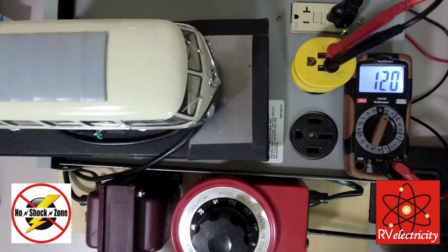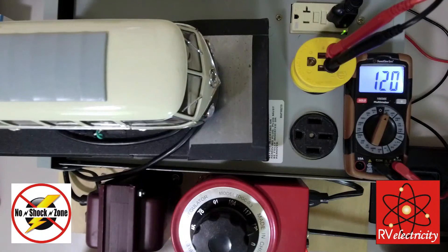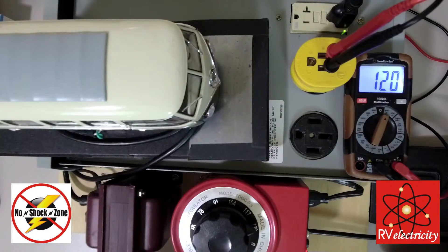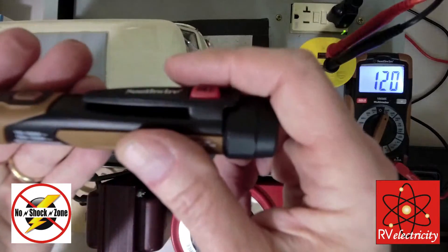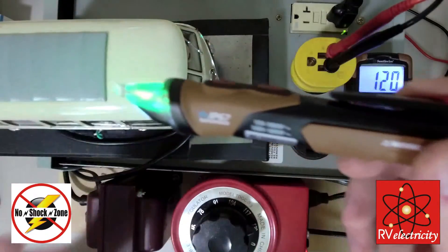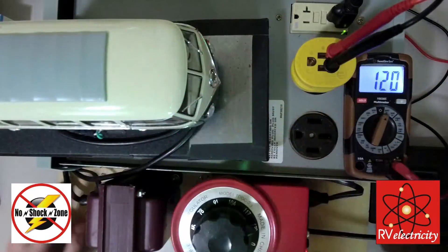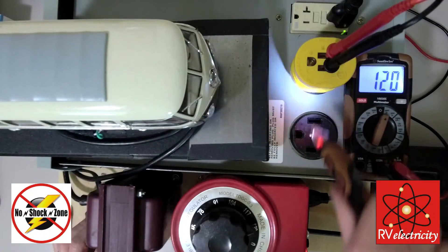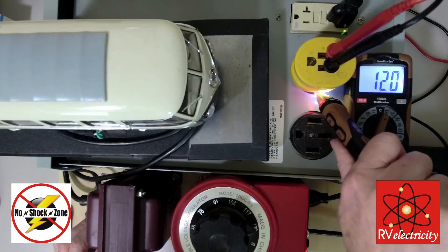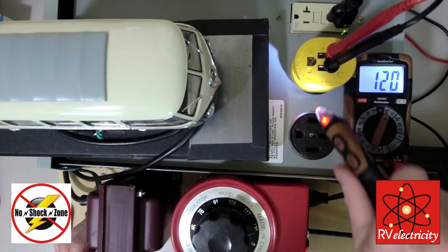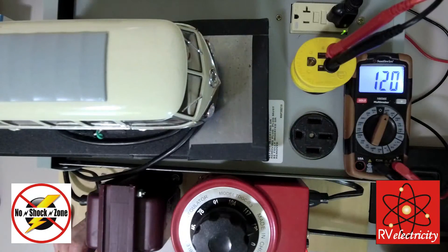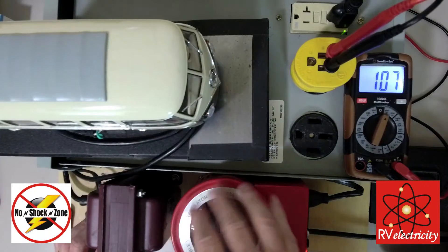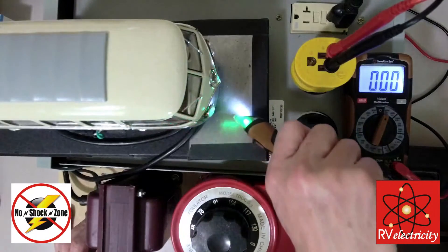So anytime you have a non-contact voltage tester, you want to first confirm that the thing is operational. So I've got this thing turned on right now. I'm going to go ahead and poke it at a known outlet because I know that outlet is hot with 120 volts on it right now. You see it's beeping at us and blinking at us. So we know that the tester has not failed and it's not going to give us a false negative. I'm going to turn our voltage all the way down here to zero.